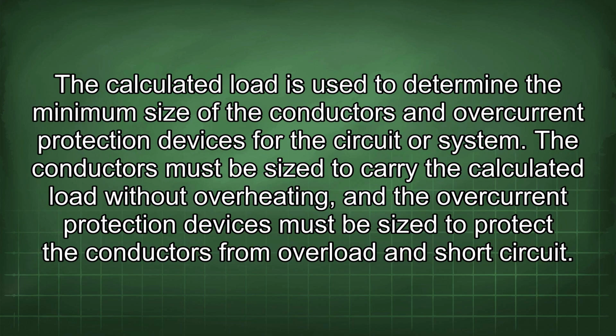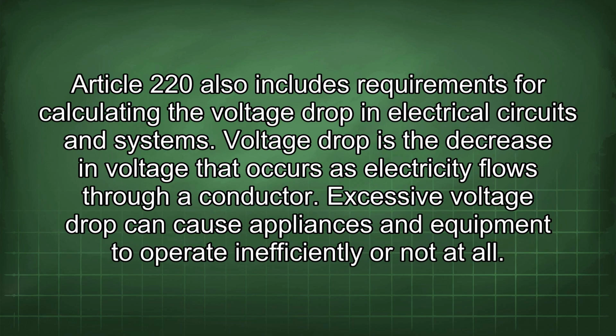The calculated load is used to determine the minimum size of the conductors and overcurrent protection devices for the circuit or system. The conductors must be sized to carry the calculated load without overheating, and the overcurrent protection devices must be sized to protect the conductors from overload and short circuit. Article 220 also includes requirements for calculating the voltage drop in electrical circuits and systems.